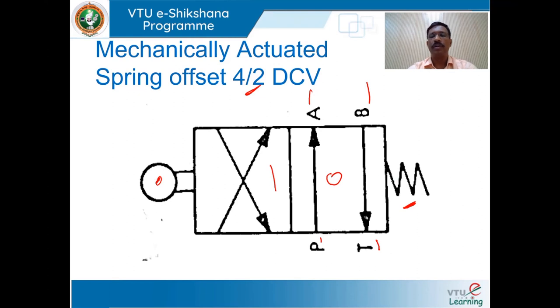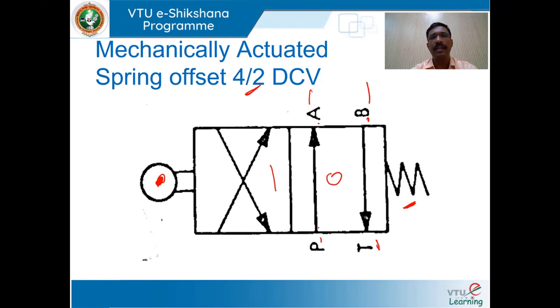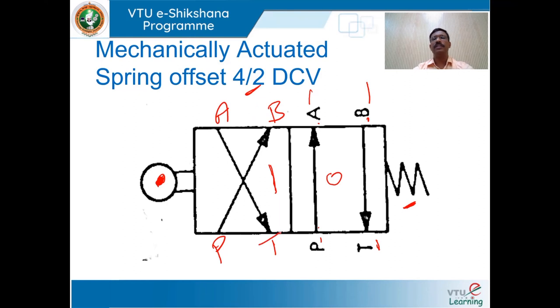In the spring-offset mode, P is connected with A and B is connected with T. When roller operated — mechanically operated — the roller is connected to the spool, and when in this envelope configuration it moves to position 1, P connects with B and A connects with T. This is how a mechanically actuated spring-offset four-way directional control valve symbol looks.